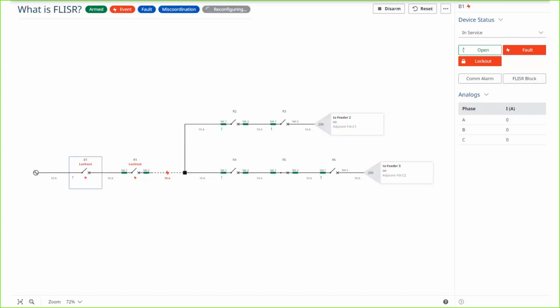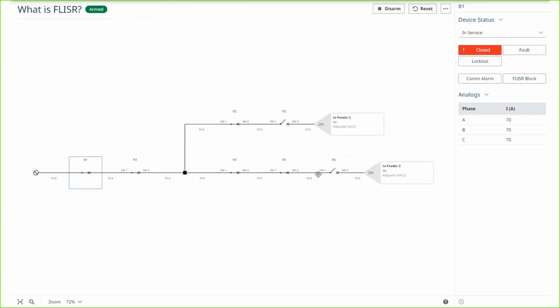So again, you're going to see a very similar reaction here. We close the breaker back in, but we do not issue an open control to recloser 1 because it's already open. So the result is the same. We minimize the impact of the outage. We restore as much load as we can.